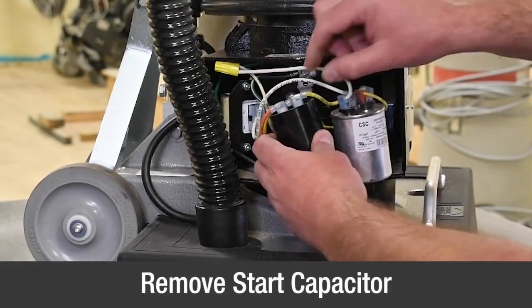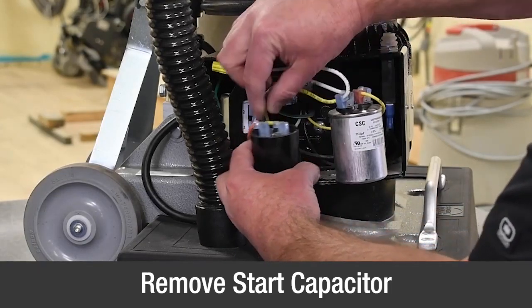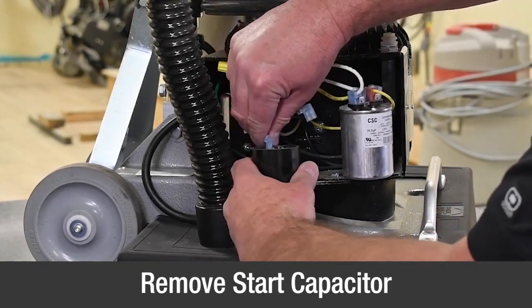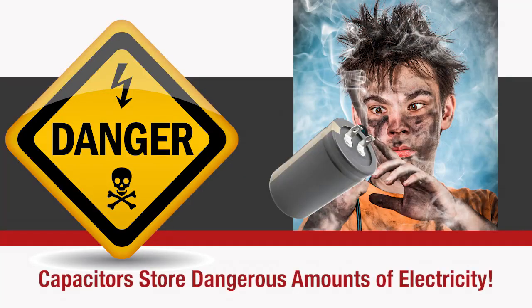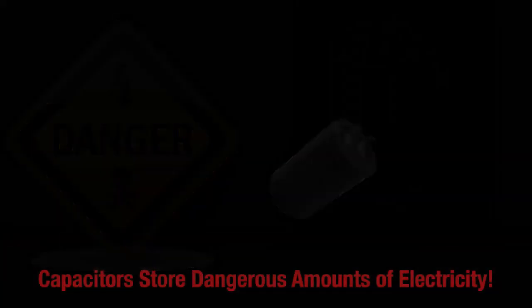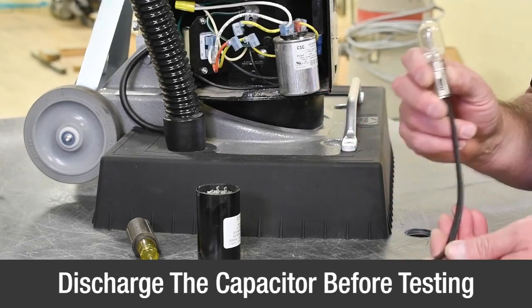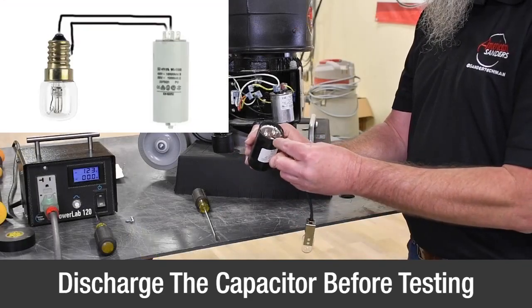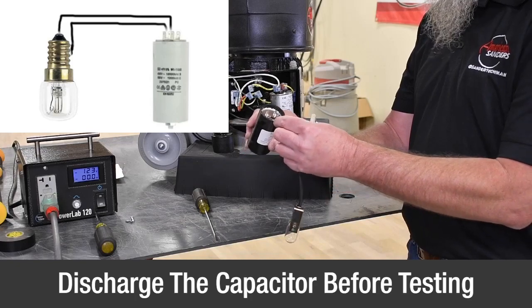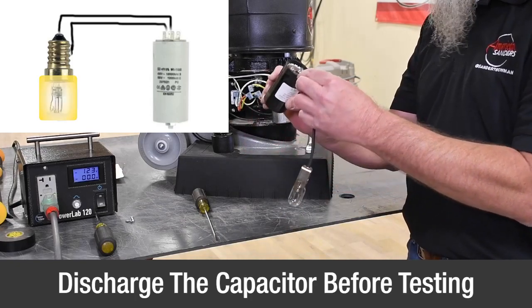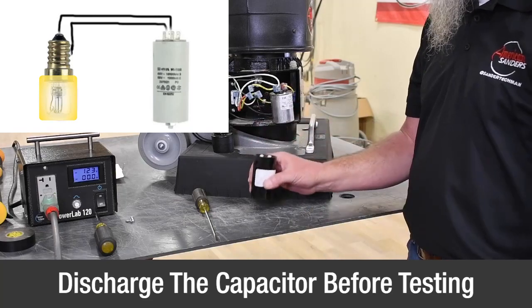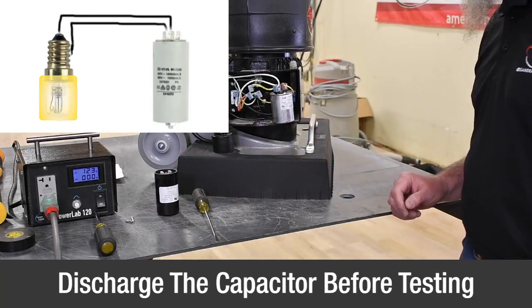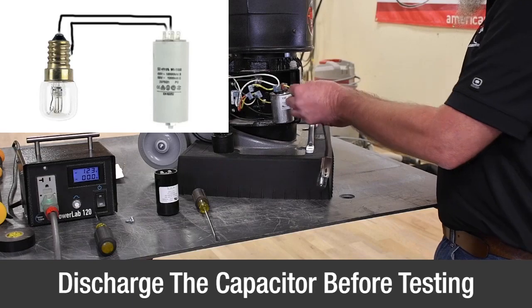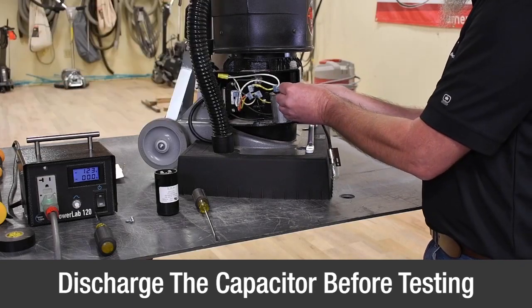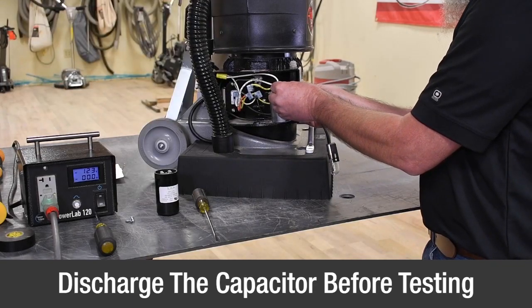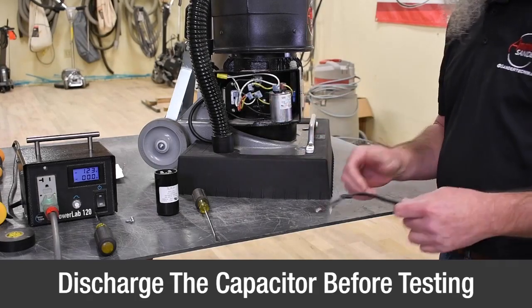To test the start capacitor, carefully remove the wire leads without touching the connectors. Start capacitors store a dangerous amount of electricity. Discharge the capacitor immediately using a suitable device such as a small incandescent light bulb with a short lead. If the bulb lights up, there is a charge in the capacitor. Hold the leads on the capacitor until the bulb goes out. Once the bulb goes out, the capacitor is discharged and safe to handle. You can repeat the same discharge process on the run capacitor.